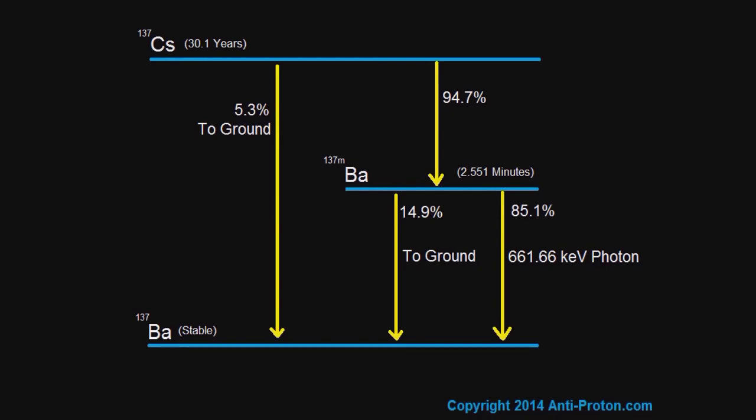And as you can see, 85.1% of the time this occurs by the emission of a gamma ray. The gamma ray that is emitted always has the energy of 661.66 kiloelectron volts. That's what we constantly measure, we use that for calibration. It's an absolutely wonderful energy to keep memorized. 14.9% it goes straight to the ground state. Barium-137m has a half-life of 2.551 minutes.